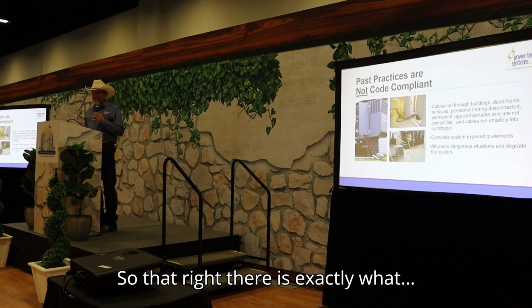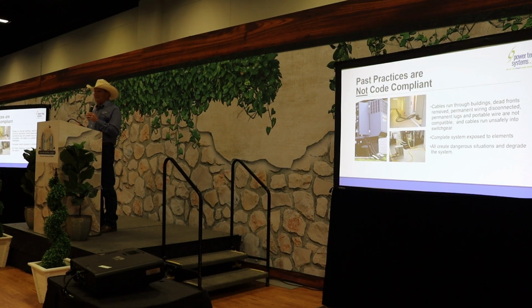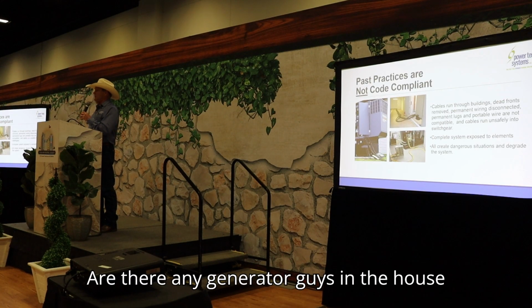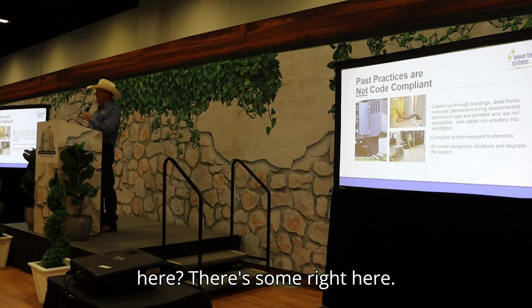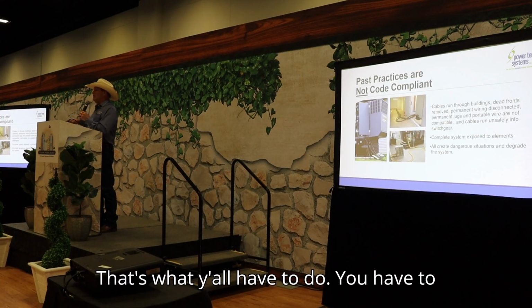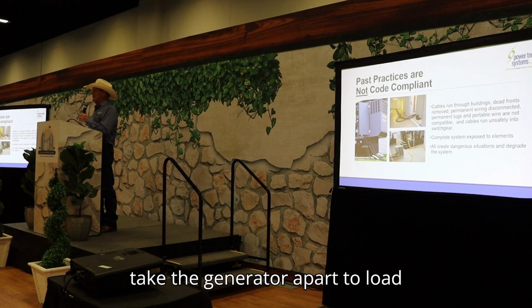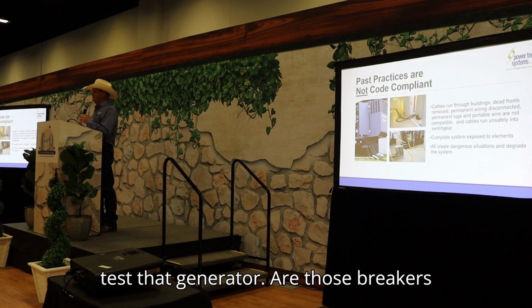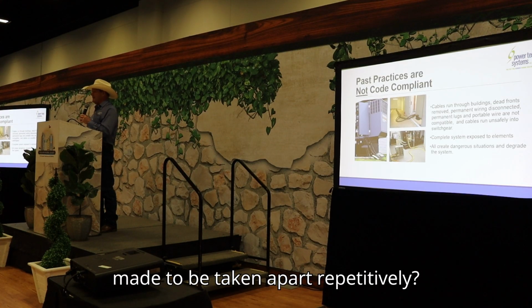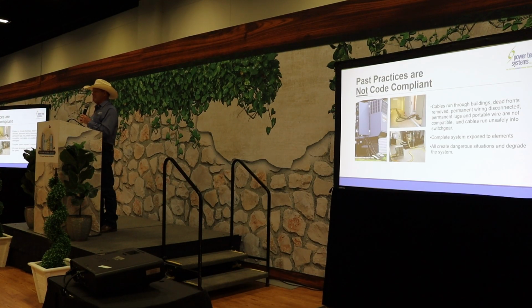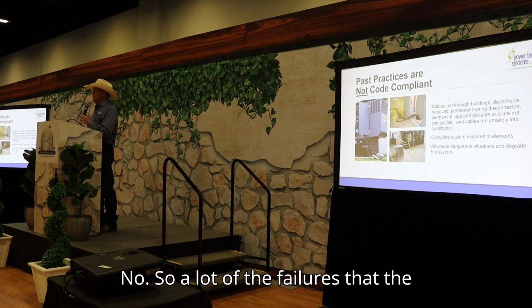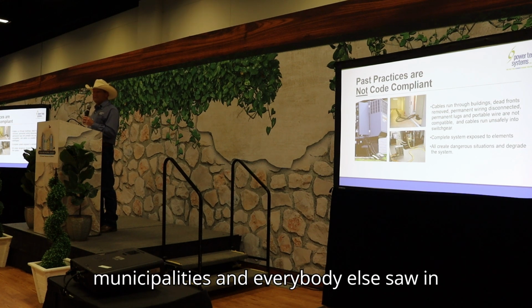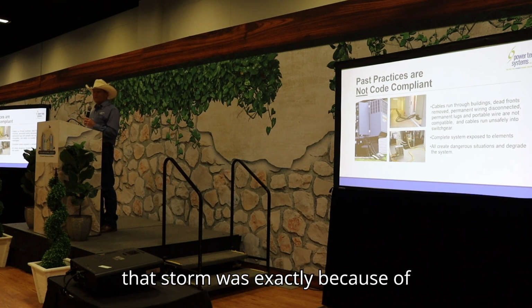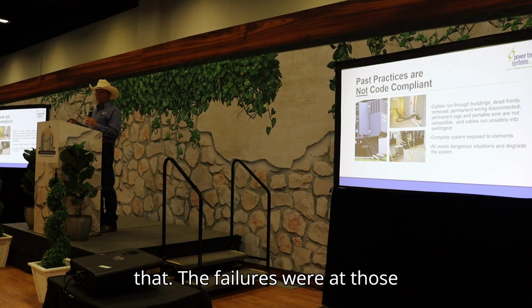So that right there is exactly what - I got any generator guys in the house here? There's some right here. That's what y'all have to do: you have to take the generator apart to load and test that generator. Are those breakers made to be taken apart repetitively? No. So a lot of the failures that the municipalities and everybody else saw in that storm were exactly because of that - the failures were at those breakers.